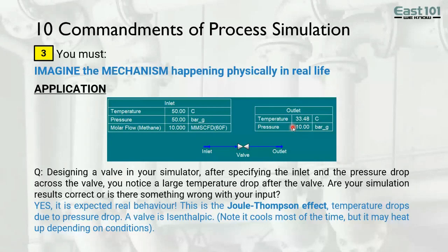So it is due to the Joule-Thomson effect, and you should be able to map this with what's going on in your facility. Most of the time in your plant, a lot of valves might be insulated; in some cases if they're not, you might see what's called sweating, meaning the valve gets cold and you get condensation on it. So it's really important to understand what's going on in real life before we map it into the simulator.